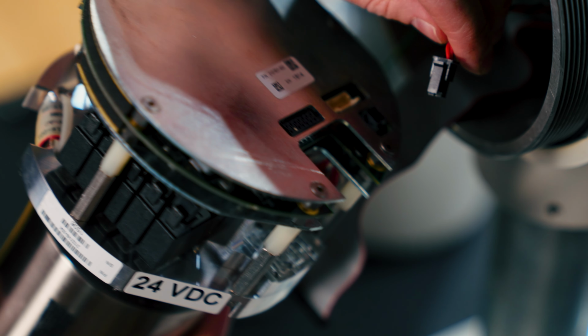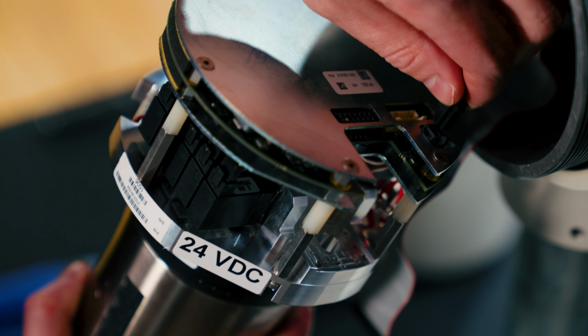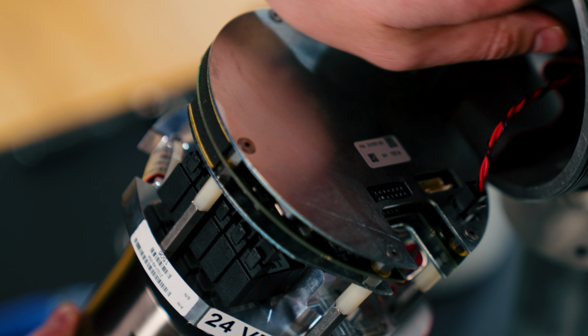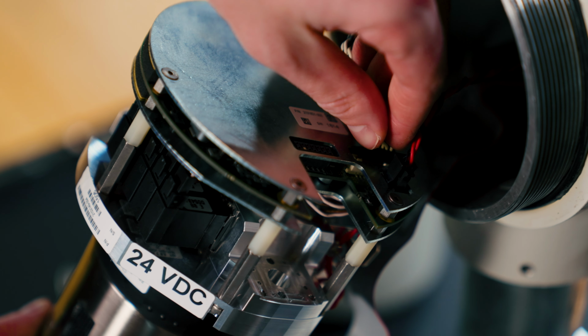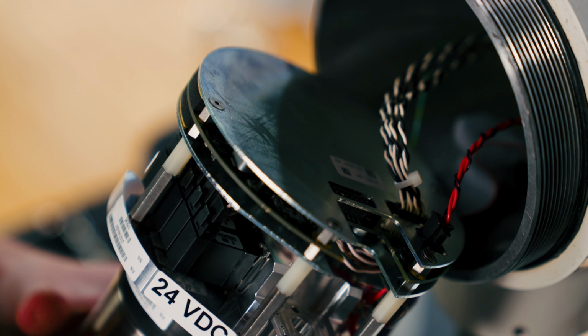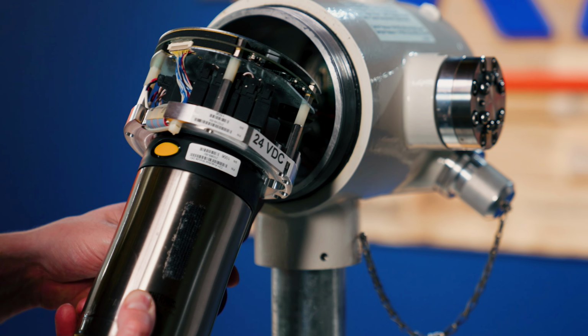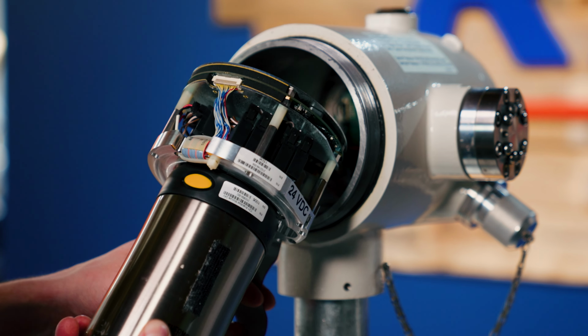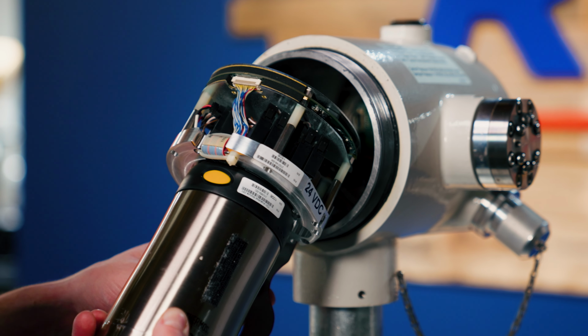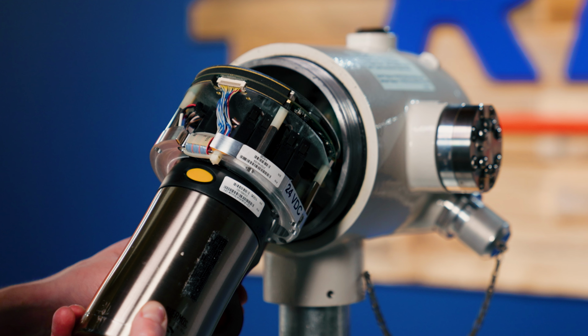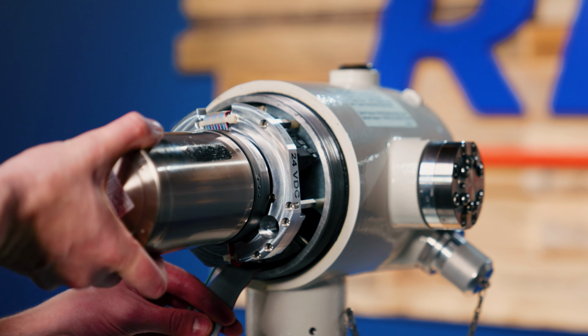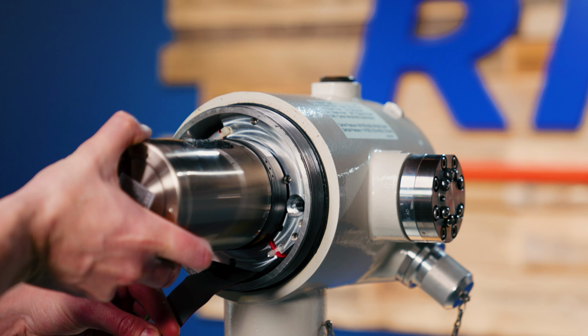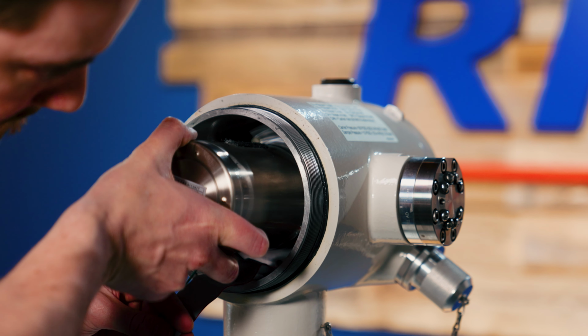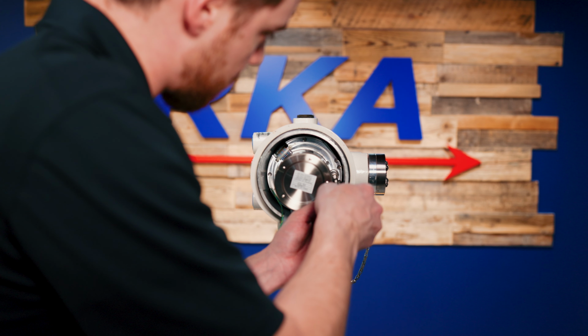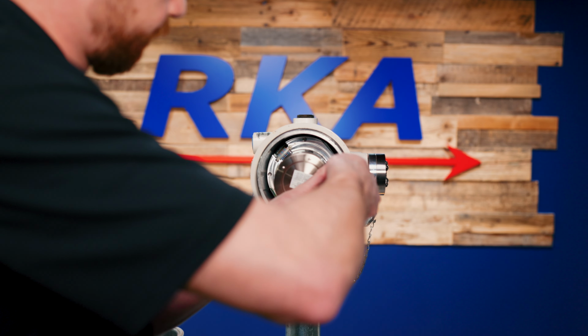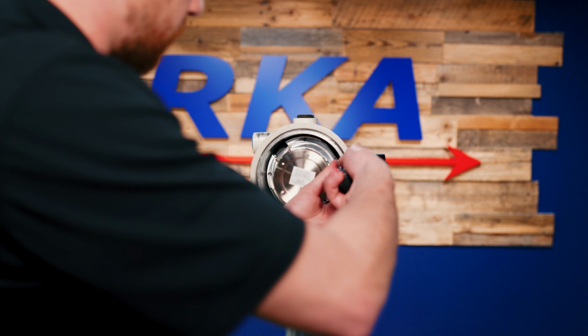Now we can reattach our cables to the back of the new module using the feed-through cable and the rear term board cable. Now we can install the GC module onto the feed-through. Be aware when putting this in, you don't want to pinch your cables into the feed-through. You also don't want to damage the ribbon cable. Now that the module is in place, we will put on our hex bolt. Snug, not over tightened.